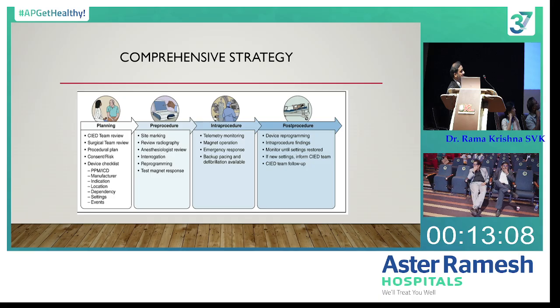You should know the indication, especially if the patient is dependent on a pacemaker, and you should be very careful. Any electromagnetic interference can lead to loss of pacing, given the dependency of the patient. During the pre-procedure, it is essential to interrogate, program the device, and test the magnet response of the device. Obviously, intra-procedure is about monitoring the patient and backup responses. Post-procedure, again, reprogramming the device, and if there are new settings, you have to inform the device clinic.